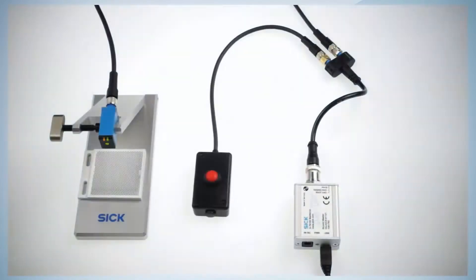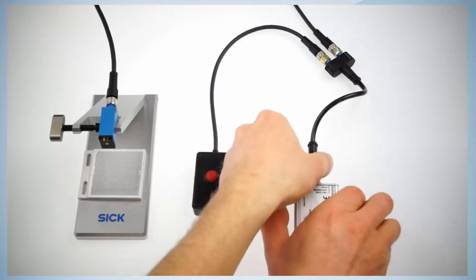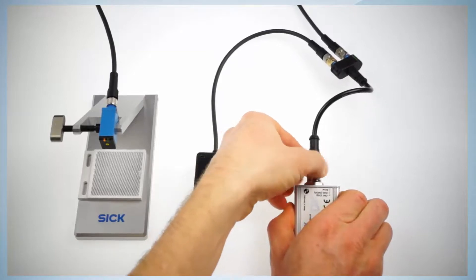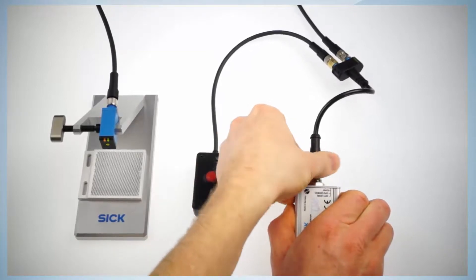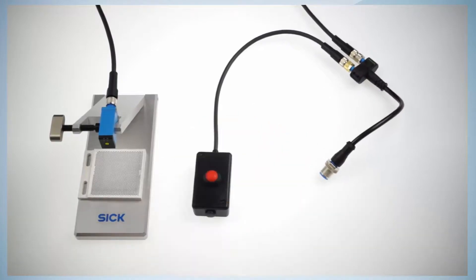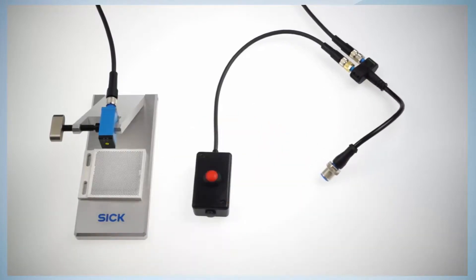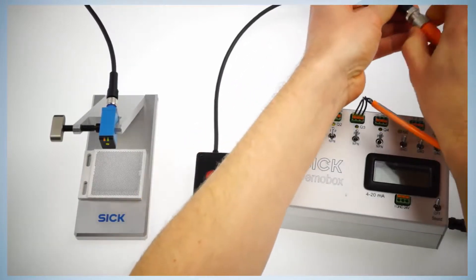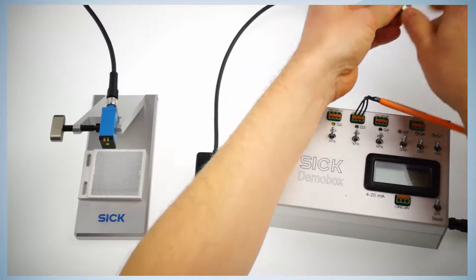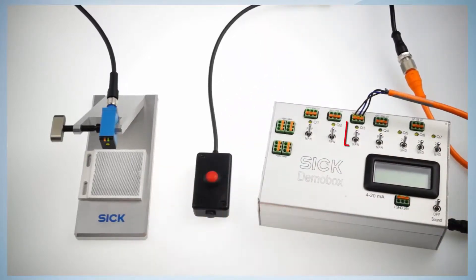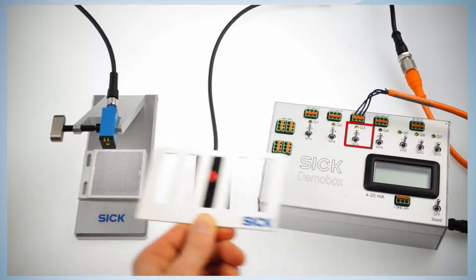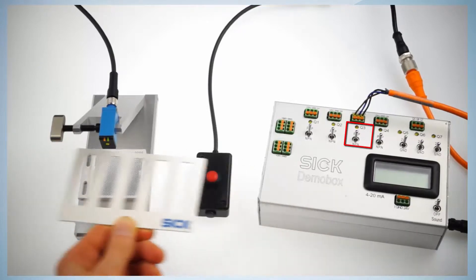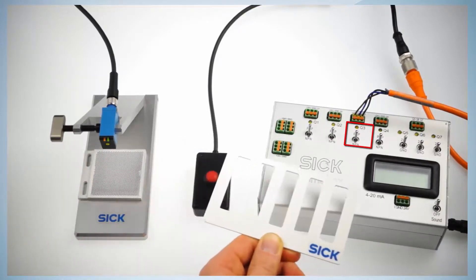One of the advantages is that this IO-Link sensor can be removed from the IO-Link network and plugged into a standard IO network. The settings of the sensor stay the same as they have been configured before. In this example, the switching output is activated after 6 bars. To show this, the sensor is now removed and connected to a standard power supply. To make sure that the setting is at 0, it is reset by the external trigger. As soon as the sensor detects 6 bars, the output of the sensor is high.